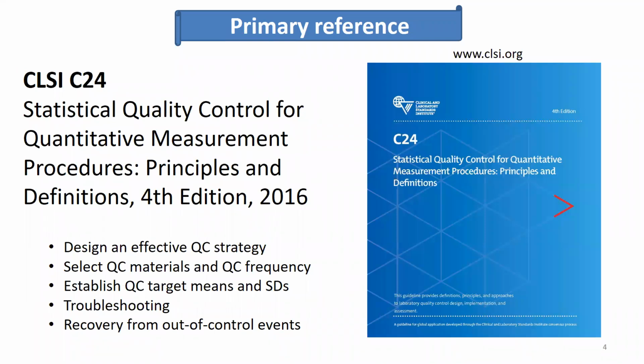The primary reference that will be used as the basis of the recommendations in this presentation is the Clinical and Laboratory Standards Institute document C24. Its title is Statistical Quality Control for Quantitative Measurement Procedures. This CLSI guideline issues recommendations for designing an effective QC strategy, selection of QC materials and frequency of QC analysis, establishment of QC target means and standard deviations, troubleshooting guidelines, and recommendations for how to recover from out-of-control events. The document can be found on the CLSI website, which I've listed the URL at the top of the slide.